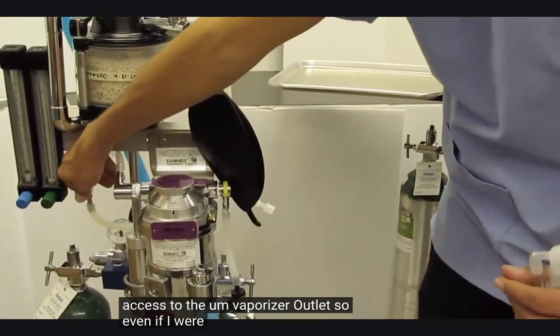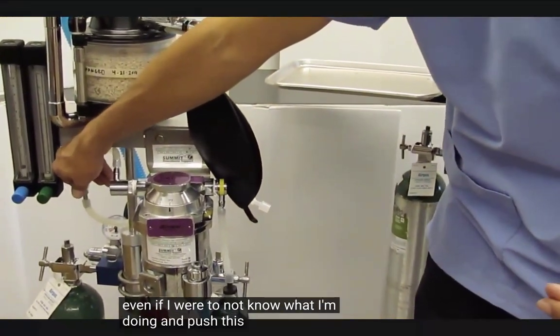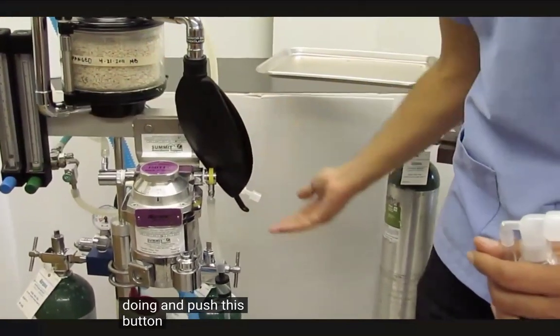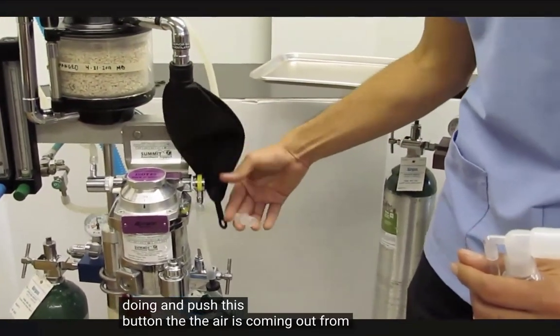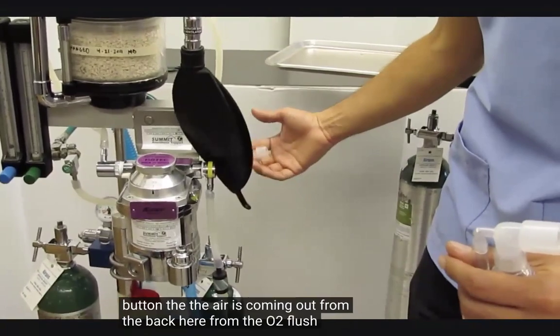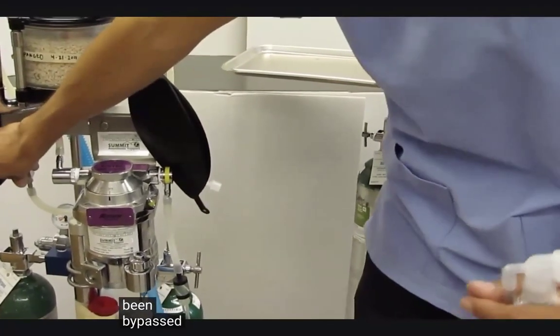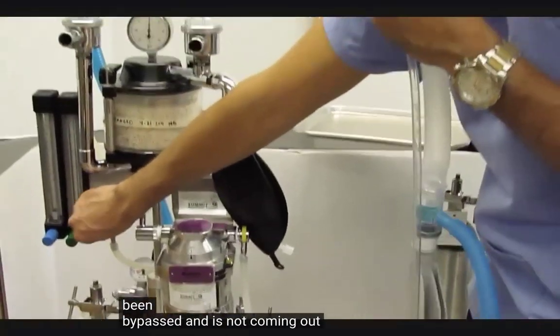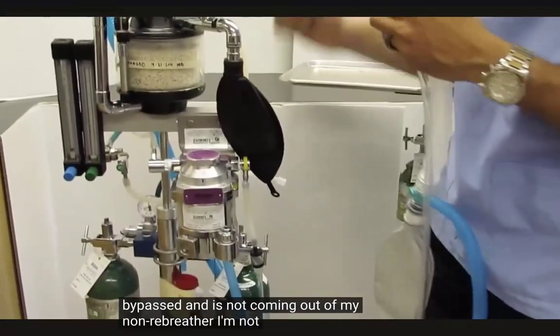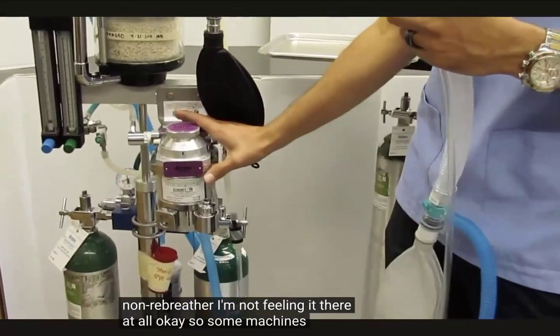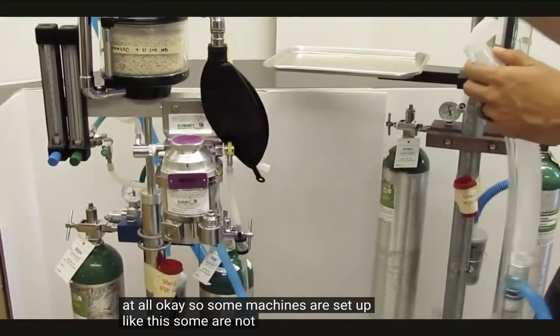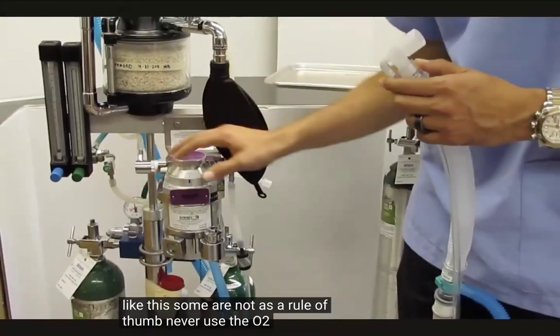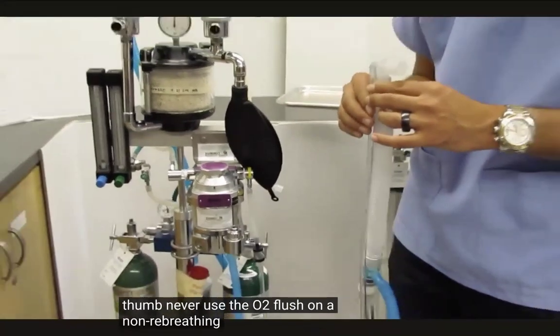So even if I were to not know what I'm doing and push this button, the air is coming out from the back here, from the O2 flush that has been bypassed, and is not coming out of my non-rebreather. I'm not feeling it there at all. Okay, so some machines are set up like this, some are not. As a rule of thumb, never use the O2 flush on a non-rebreathing circuit.